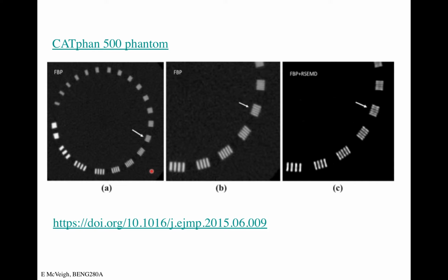It turns out in CT it matters. If you bring this thing down towards the center, you're going to have higher spatial resolution than when it's out at the edges. And this goes back to your question, how many views do I need? If you want spatial resolution in your field of view way out at the edges, you need a lot of views. Basically, inside a certain circle, you have a sufficient sampling for a given number of views. When you set the number of views, that sets the diameter of that circle inside which you're adequately sampled. And outside that, you get aliasing.